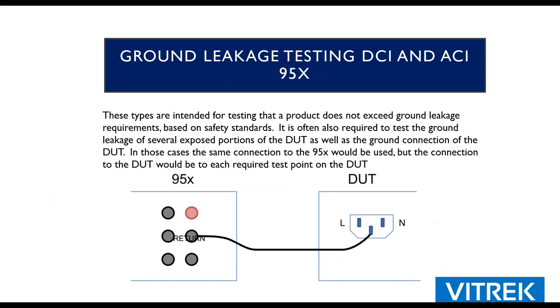All right, so this is another test, not as common, but there's going to be a handful of standards that require it, and this is something we can do with the 95X. As you know, although there are standards for wiring, you could have an outlet that has a floating ground. Oftentimes, you will have line and neutral crossed in an outlet. In North America, with NEMA 5-15, the bigger slot on the left is supposed to be neutral. The one on the right is supposed to be line, which is going to be a smaller gap. Sometimes those are crossed. So some of the standards require single fault testing. So let's pretend ground isn't there. You put the 95X in where the ground is supposed to be, and you measure that current flowing to ground. It's a single fault failure test, and that's something that we offer.